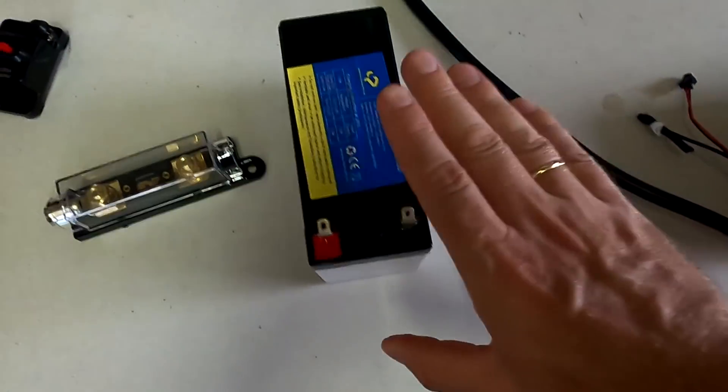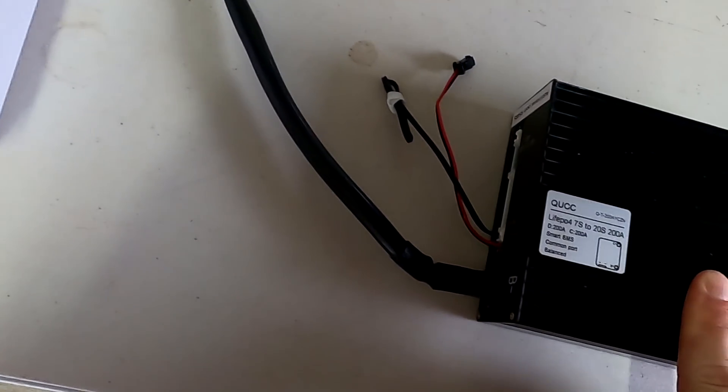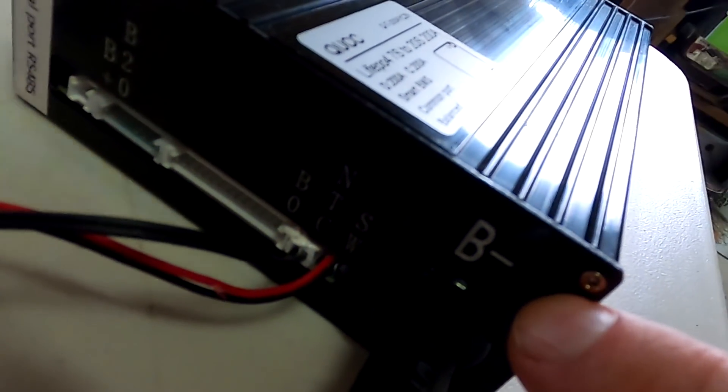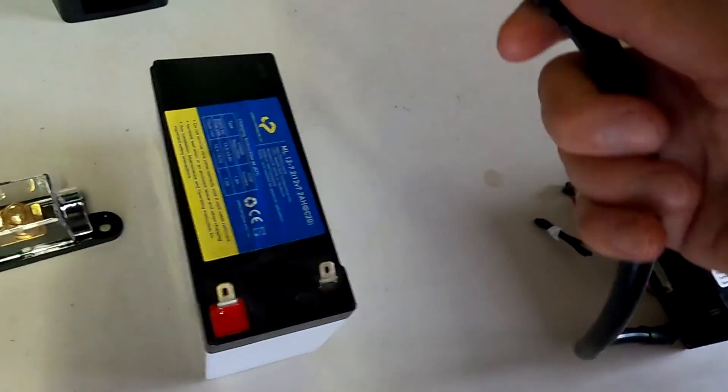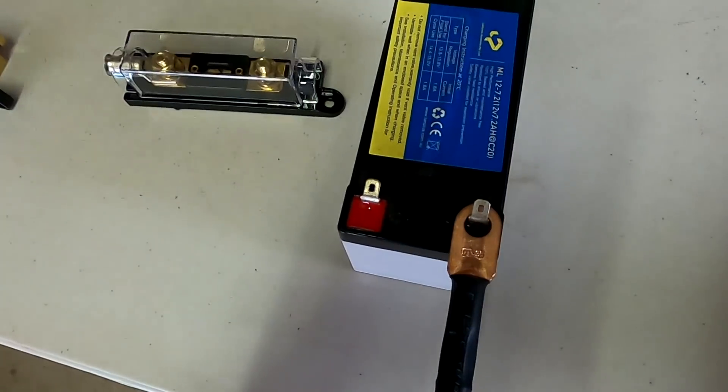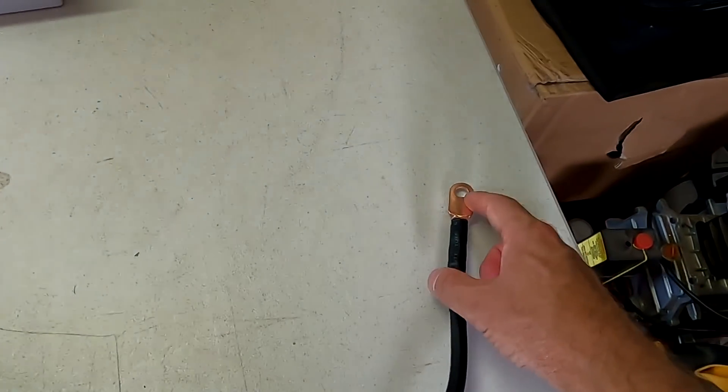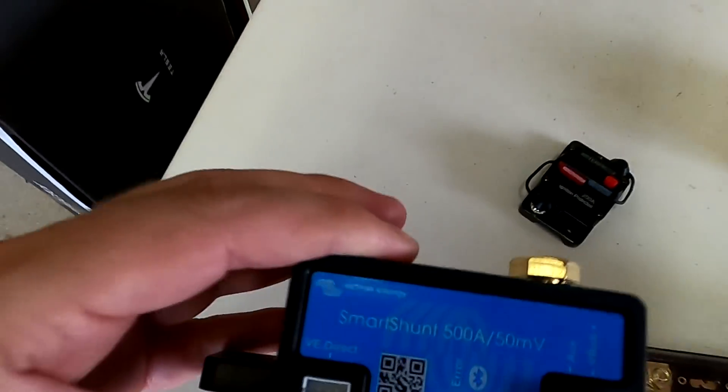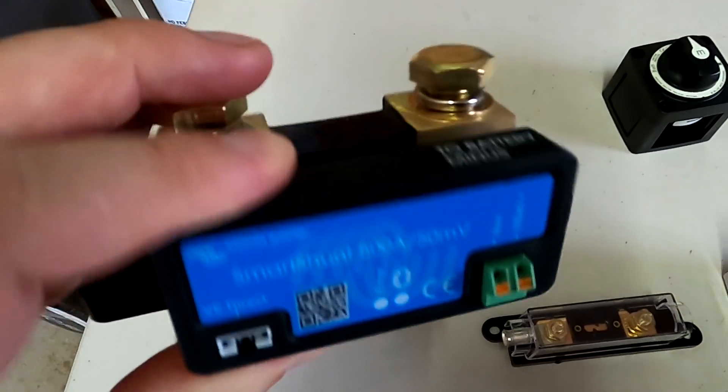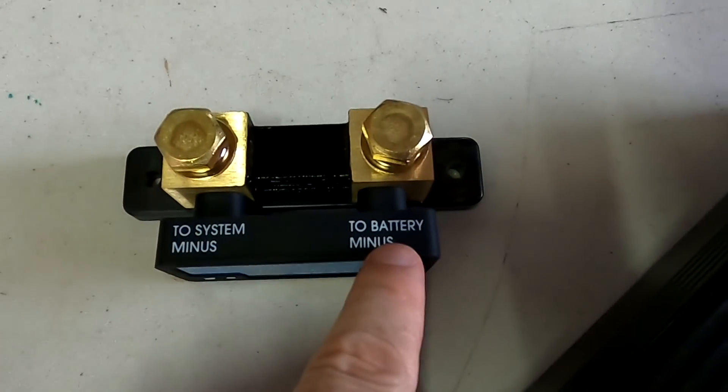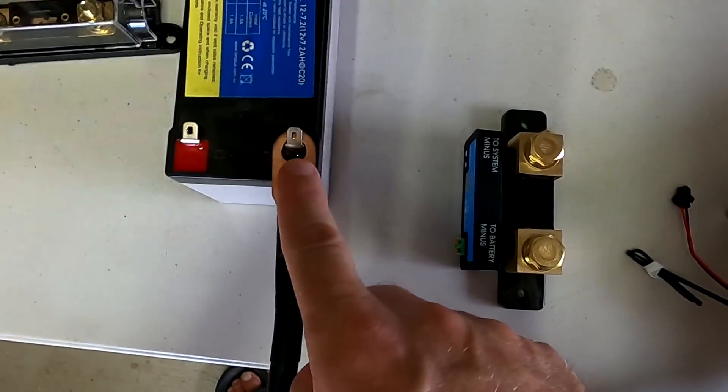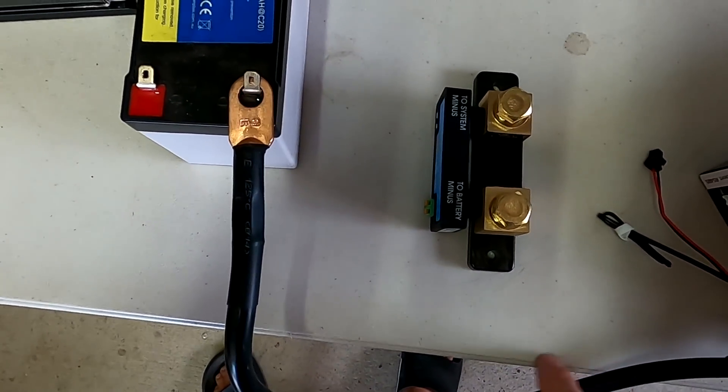And then we've got the JK BMS, 200 amps. What I don't understand now is, see, we've got our battery. Let's pretend this is our lithium iron phosphate battery. The manual of the BMS says this cable here needs to be connected to B minus, so this one needs to go to the negative side of the battery, right? And then you connect this one to the negative side of your inverter and the charge controller. All good. This Victron Smart Shunt actually claims the same: to battery minus. This one needs to be connected to battery minus as well, but not in parallel to this one.